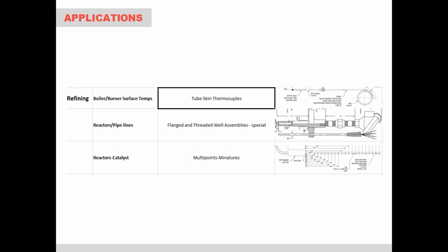Refineries have a wide range of temperature sensor requirements, including boiler and burner surface temperature assemblies with weld pads to monitor for hot spots in the tubes, flanged or threaded thermowells for use in reactors, as well as tanks and pipelines throughout the various units found in a refinery. We also provide a variety of special multi-point assemblies whereby a single tube can contain as many as 40+ measurement points along the length of the assembly.